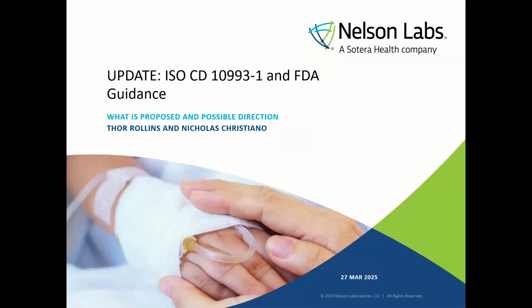Nick, do you want to take this one in the beginning? Yeah, so this is interesting. I think in some cases, the reason why we went this way is we know as manufacturers that we are not ignorant to the fact that end users, practitioners are potentially overusing devices or using devices off-label, right? So I think this is a healthy approach to trying to capture as much risk mitigation as possible without having to, kind of almost like, I think of it as like a sterilization validation, right? Without over challenging, without being unrealistic and actually kind of walking into the lines of contraindications, and knowing that these are reasons why this device should never be used.